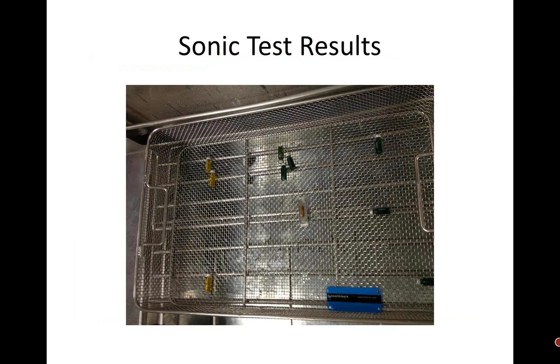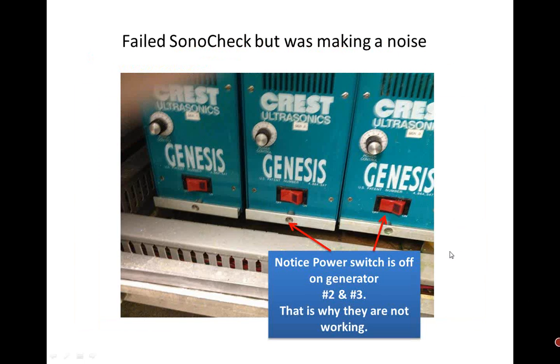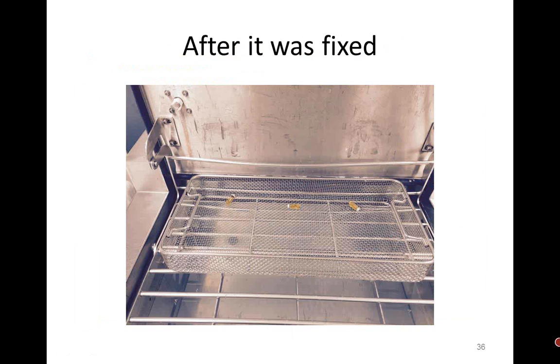This next picture deals with my product, unfortunately. Yellow means you've had cavitation, green means there has not been sufficient cavitation, and our TOSI indicator is in the middle. I checked this tank and we were only getting cavitation in one-third of it. It turned out that underneath, somebody had shut off two of the generators, so two-thirds wasn't working while the other side was. We changed it, ran my SonoChecks, and confirmed there was cavitation working.